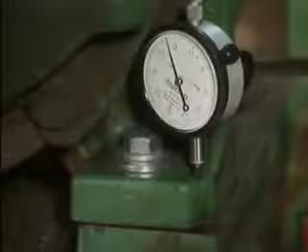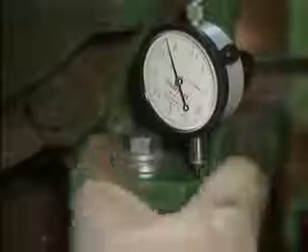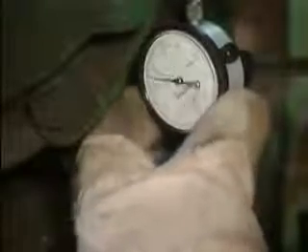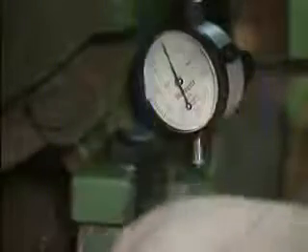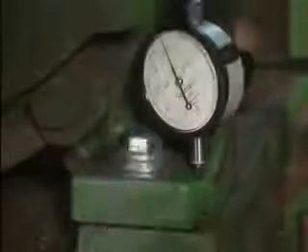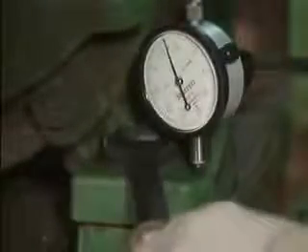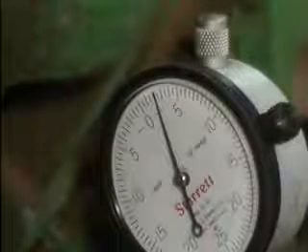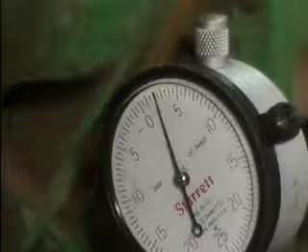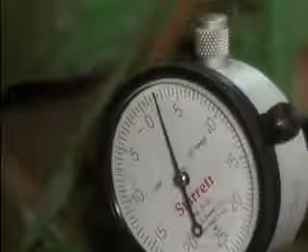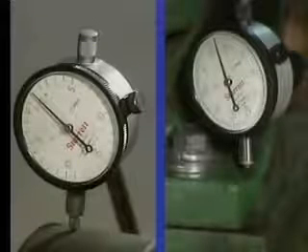Each dial indicator is mounted so that its stem is partially compressed before the indicator is zeroed. Doing this ensures that each dial indicator will be able to detect movement during the procedure. Next, the hold-down bolt on the first foot is loosened, and the dial indicators are checked. If either dial indicator detects more than the allowable limit of movement, which at many plants is 2 mils, then the foot is soft. To understand why 2 dial indicators are preferable, we need to look at some illustrations.